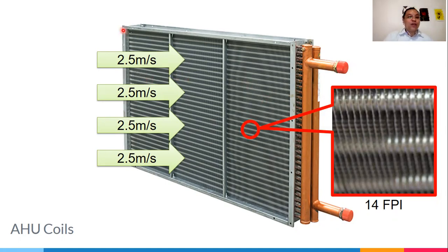Okay, so to give you an estimated size of your coil, no, malapit sa katotohanan, you just get your airflow rate and you divide it by 2.5 meters per second. That would give you the face area of your coil. Okay, if your velocity is lower than this one, you will have more heat transfer. But if you have higher velocity, you have less heat transfer. So yun lang yun, no? Your heat transfer will be dependent on your velocity.